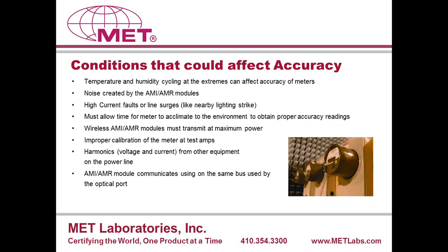So in general, just some of the conditions that would affect the accuracy: temperature and humidity cycling, extremes, noise being generated. It's an intentional radiator, an AMI module, a wireless module within the unit that could cause problems with the metrology, depending on how that's configured into the meter product. Current faults or line surges, voltage spikes simulating sort of nearby lightning strikes, or fault currents that may run through the meter or in close proximity to the meter.